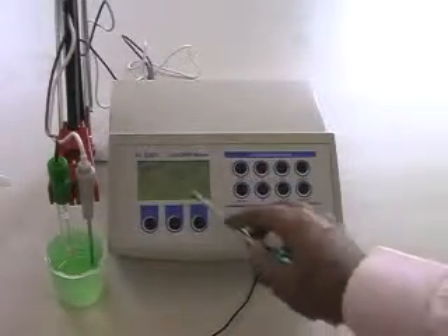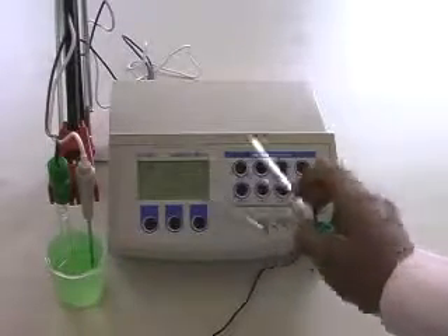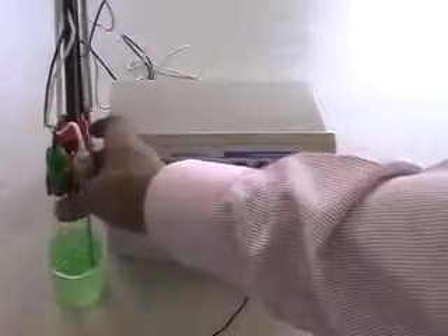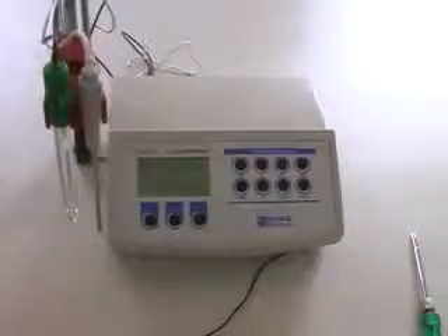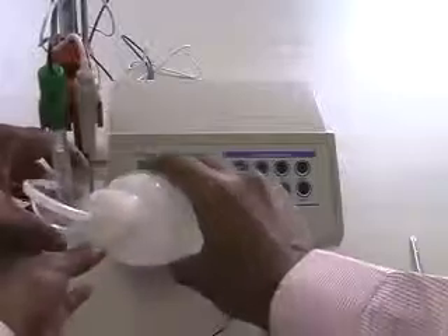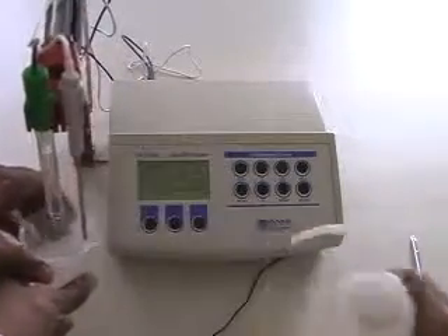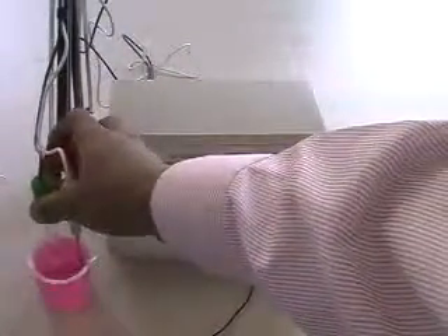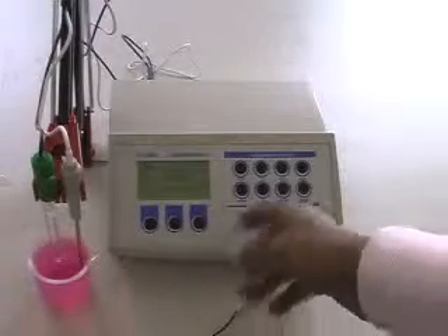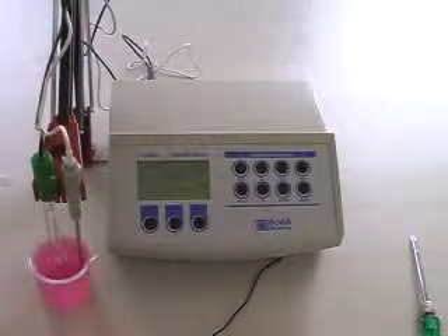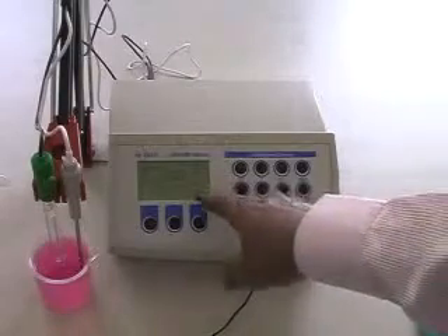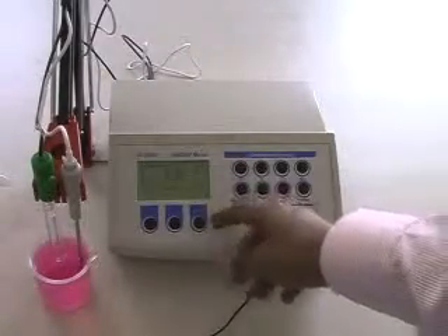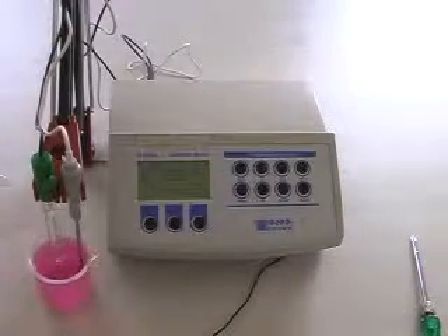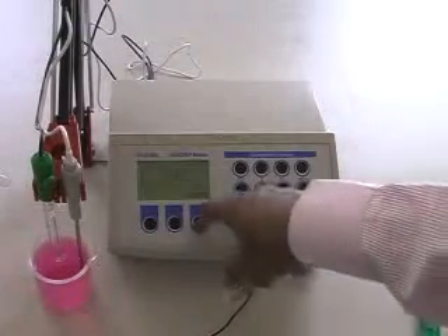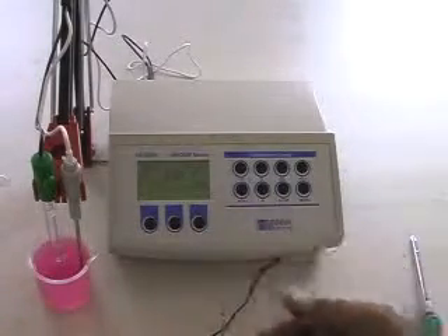Now the instrument will show the next calibration point, that is 4.01 pH, buffer 2. Before this, you have to clean your electrode with a small amount of distilled water, and then place your electrode and temperature probe in the 4.01 buffer. So now your instrument is getting calibrated for the second buffer. After some time, the instrument will show the confirm here. At that time, you have to press the confirm button. So now this is a confirm. You have to just press the confirm. Now you have calibrated your instrument for 2 points.